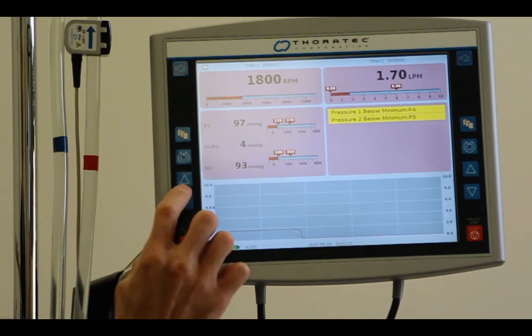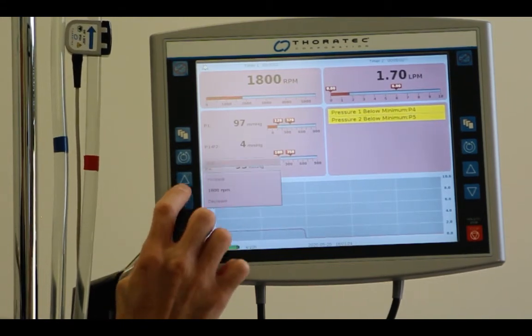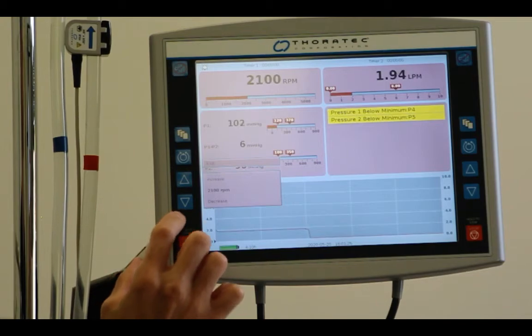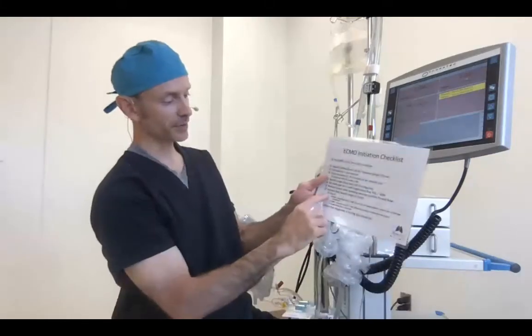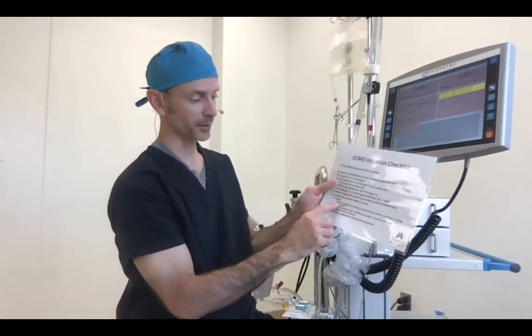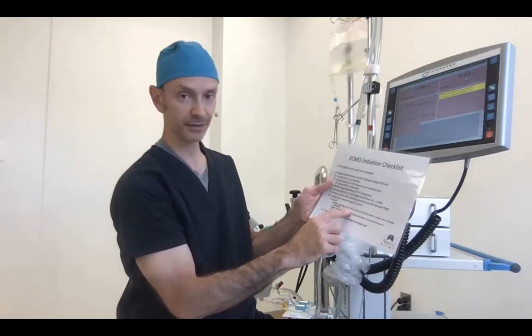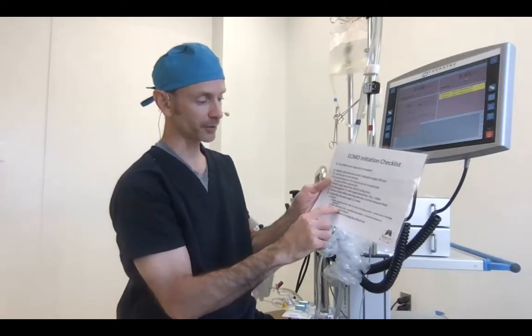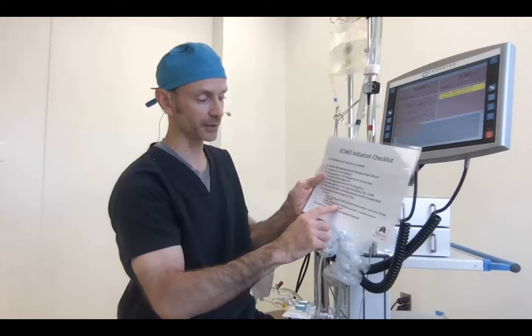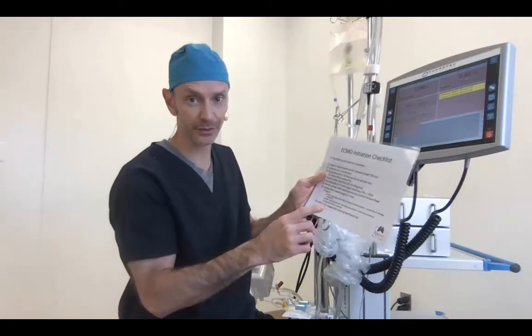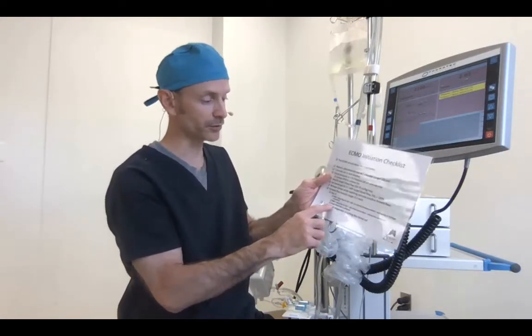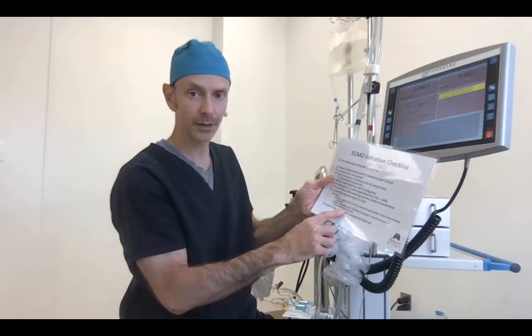So now I can slowly step up our flow, enter the RPMs, increase our flow, and I'm going to increase until I reach one of these 3 conditions. My RPMs are greater than blood flow and the line pressure is less than 300, or my RPMs are greater than blood flow and the arterial line pressure is greater than 300. Both of those tell you you've got a resistance problem, or you reach your targeted blood flow.